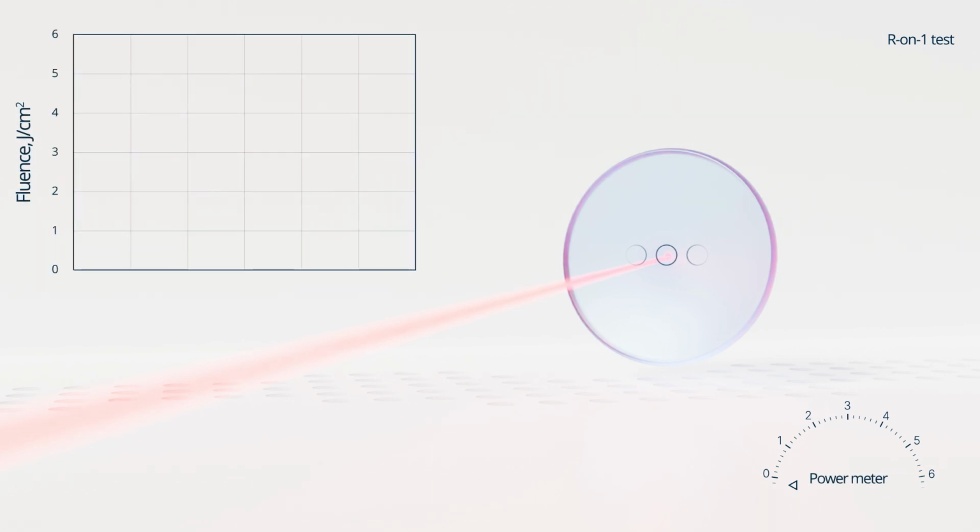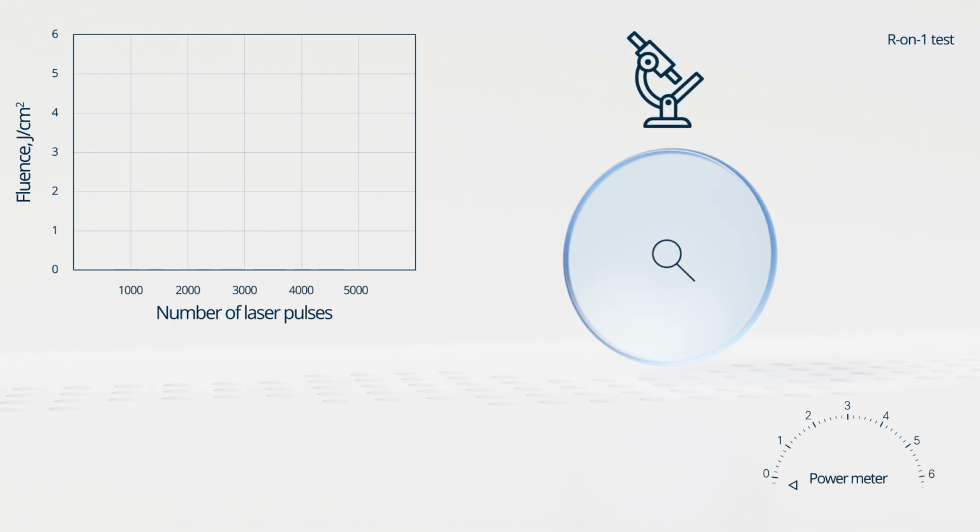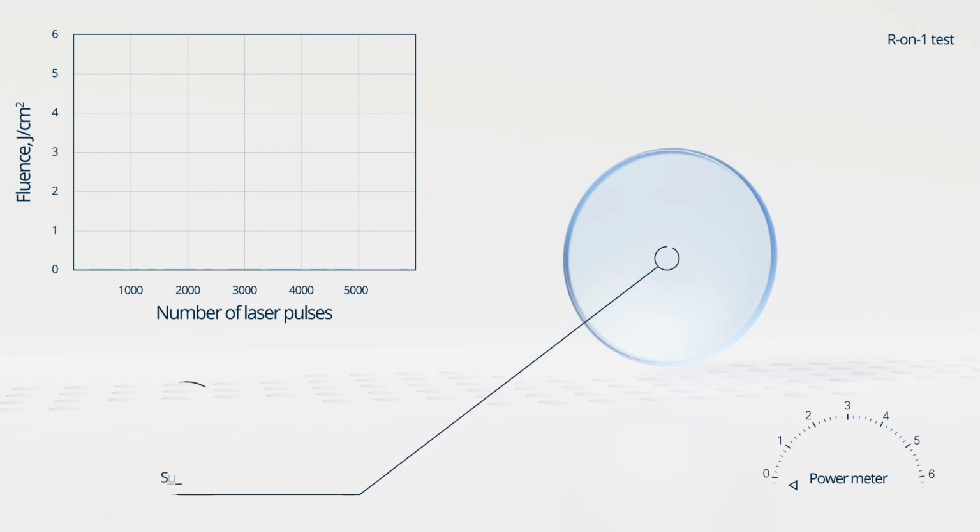The first test site is now exposed to a burst of weak laser pulses and then inspected with the microscope again. The status of the irradiated site is identified as either survived or damaged. If no damage is found, the intensity of the laser pulse is then increased and the test site is exposed again. The ramping of the laser irradiation level continues by increasing laser power in either a linear or non-linear way.